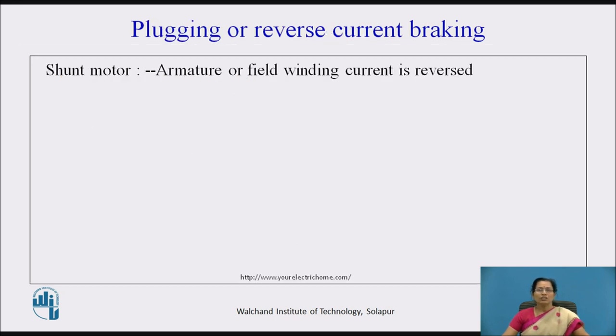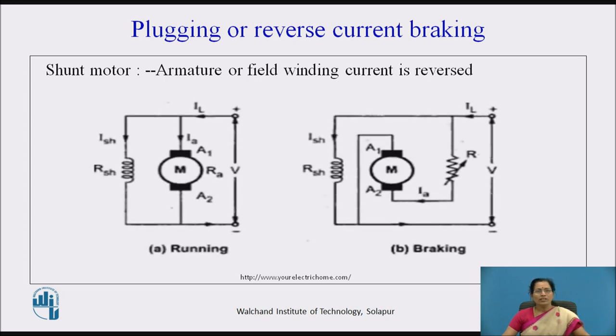For plugging or reverse current braking of a shunt motor, the armature or field winding current is reversed. In the diagram, the armature connections are reversed: A1 is connected to the negative terminal and A2 is connected to the positive terminal. So the current direction is reversed, that is upward. The torque created due to this connection is reversed, which creates braking on the motor and reduces its speed.